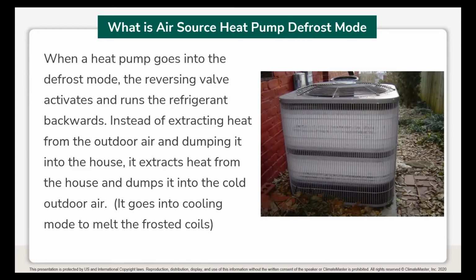A heat pump, when it is heating the home in the wintertime, needs to get rid of the buildup of frost that occurs on the outdoor coil when it is in the heating mode. So we reverse a valve and actually go into the cooling mode, using the indoor heat to melt, through the refrigerant lines, the frost that's on the outdoor condensing section. It's absolutely inefficient to go into the cooling mode before allowing the heat pump to go back to heating your home. Ground source heat pumps don't suffer from the fact that air source does need a defrost cycle.